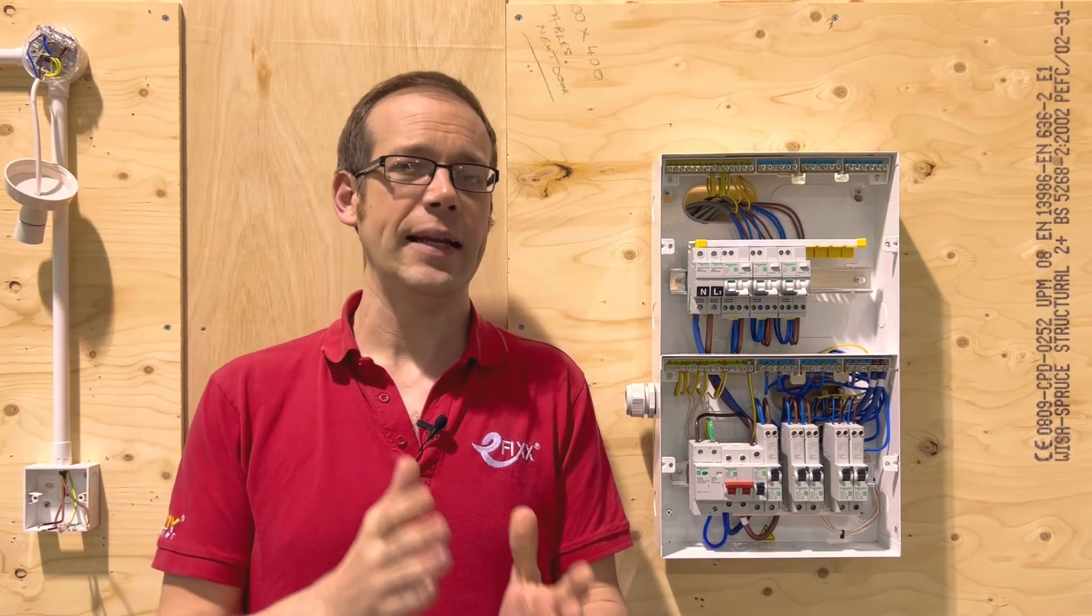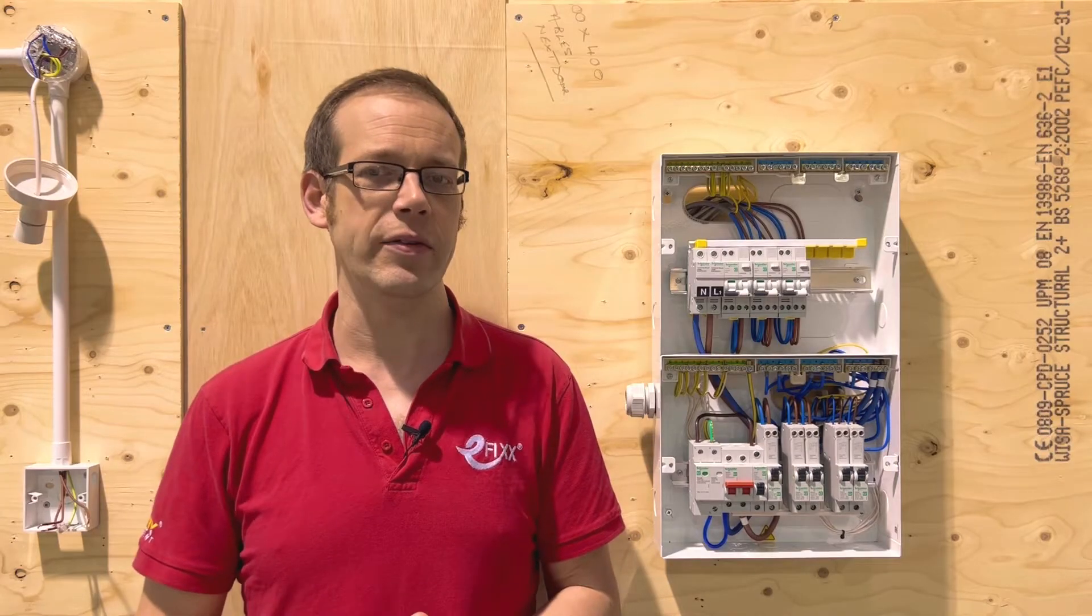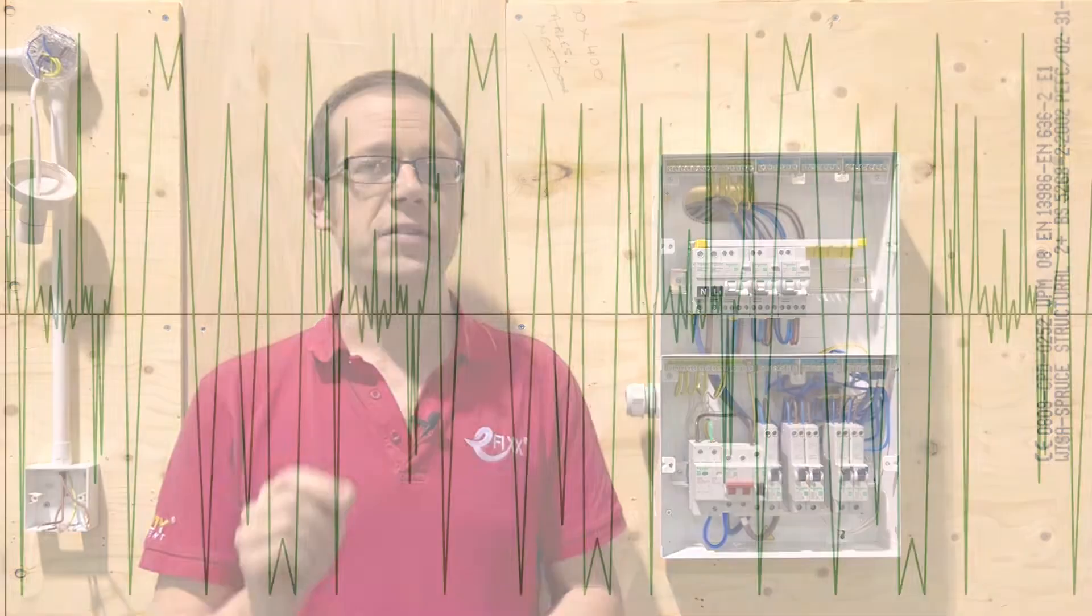Well the protective component in an AFDD is a little different to previously considered types of protective device. When an arc fault occurs it creates an instability in the current waveform of the circuit and turns it from looking all nice and smooth into a jagged mess as the current shoots up and down to create and maintain the arc.